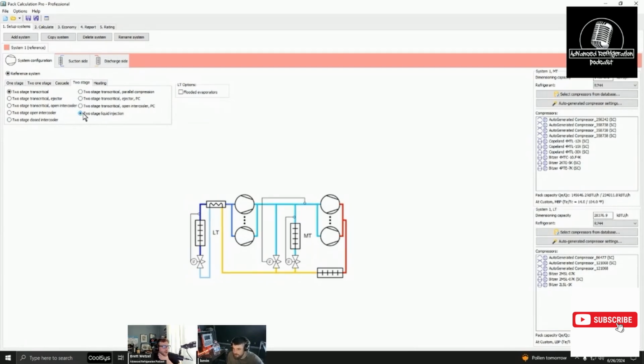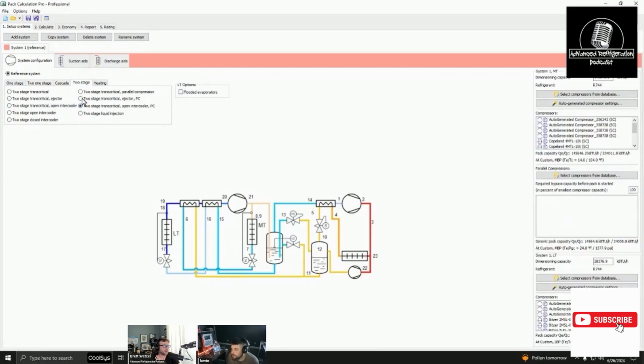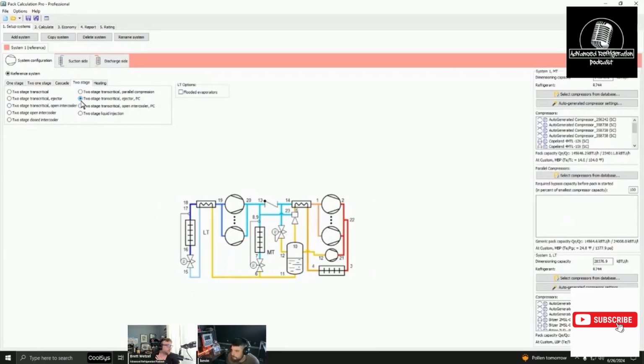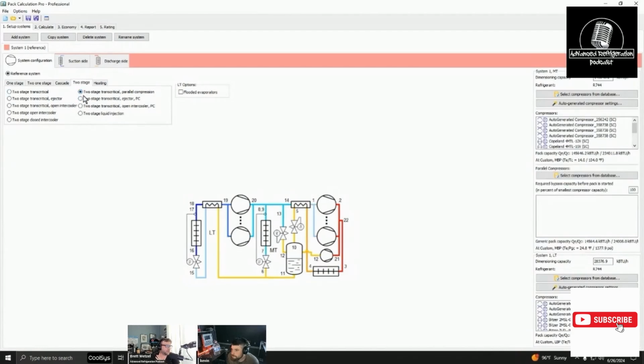But look, as you start adding stuff - this is a 2-stage liquid injection. So there you can figure out exactly how much capacity you would need based off of that if you wouldn't have the heat exchanger, right? Really? Yeah. And then you have 2-stage transcritical ejector with parallel compression, then 2-stage. What's cool is it gives you an actual readout.